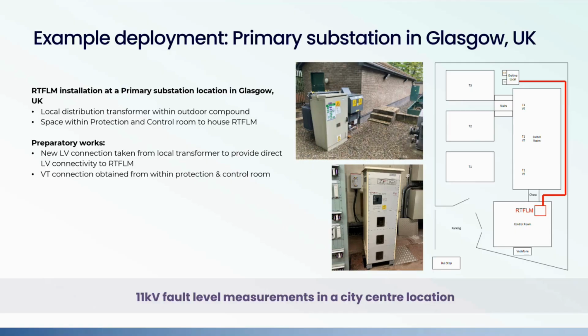The real-time fault level monitor is rated for indoor use only, so it has to be housed indoors. At this site, we identified space within the protection and control room. We ran a new connection from the LV distribution board of that local transformer, and you can see the route that we ran it around the switchgear building into the protection control room, and we terminated it just behind the real-time fault level monitor, on the wall behind it.